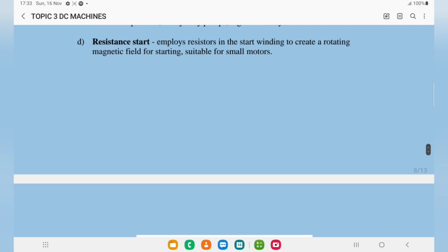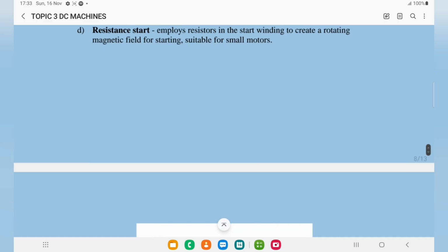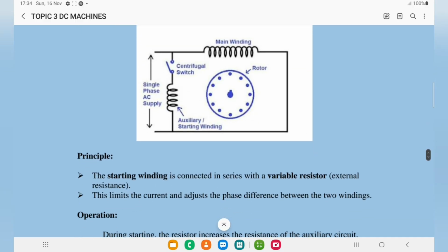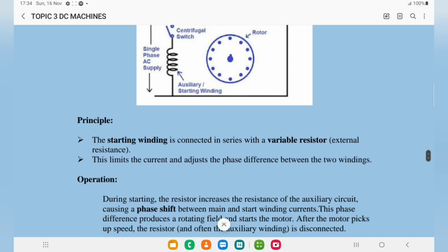The resistance start employs resistors in the start winding in order to create a rotating magnetic field for starting, and it is suitable for small motors. We can look at the circuit also. It has a main winding, a centrifugal switch, an auxiliary winding, and also a rotor. When you're talking about the principle of operation or the physical design, we just look at how the components are connected. If you look at that circuit, the start winding is connected in series with a variable resistor, and this limits the current and adjusts the phase difference between the two windings.